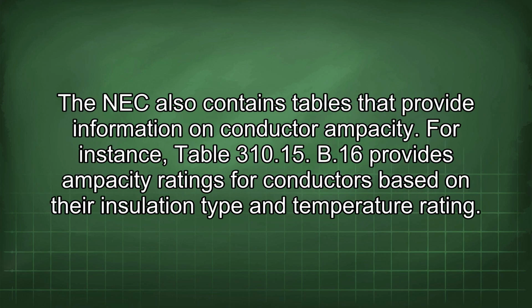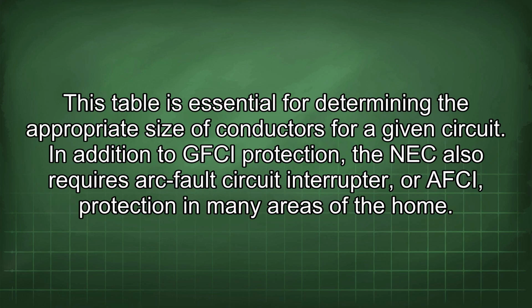The NEC also contains tables that provide information on conductor ampacity. For instance, Table 310.15(B)(16) provides ampacity ratings for conductors based on their insulation type and temperature rating. This table is essential for determining the appropriate size of conductors for a given circuit.